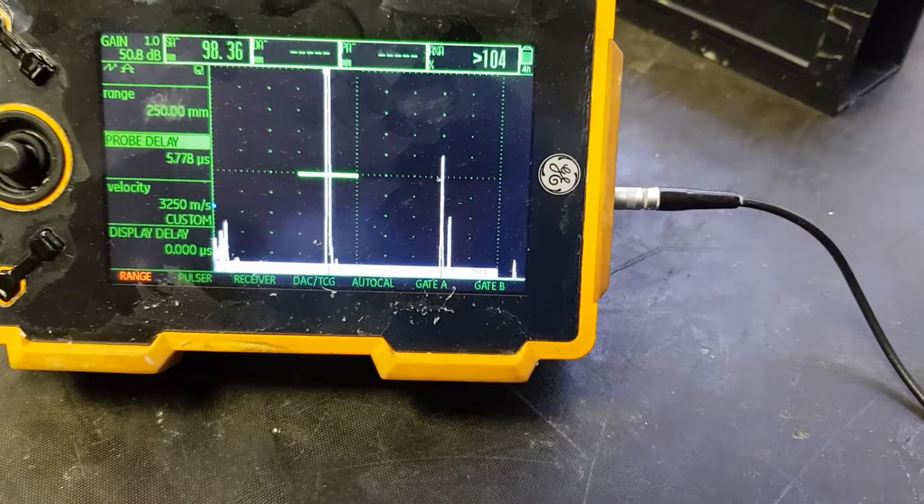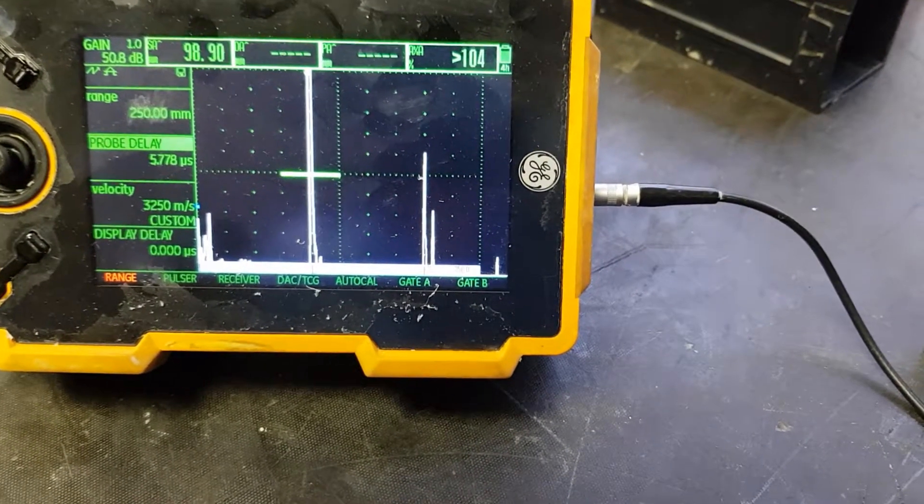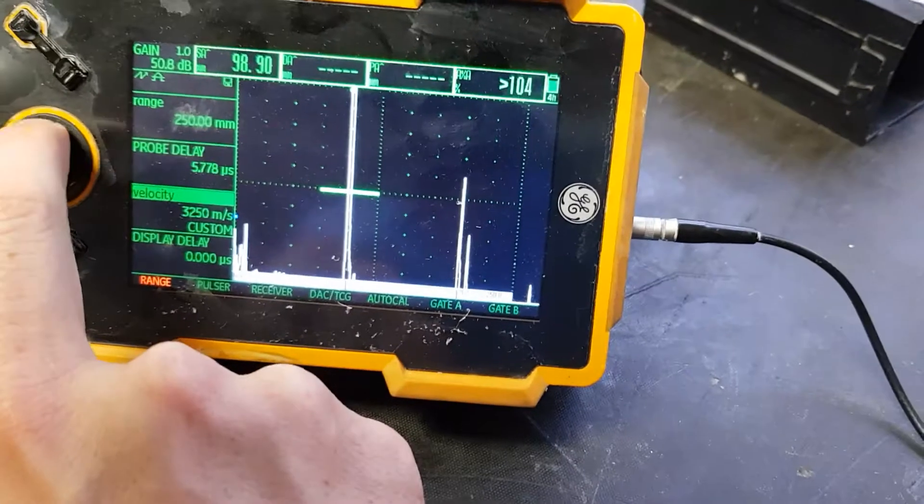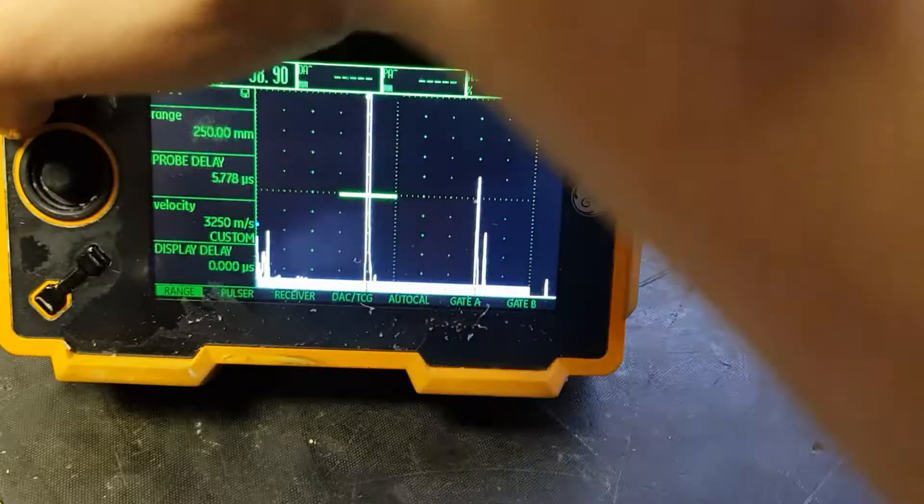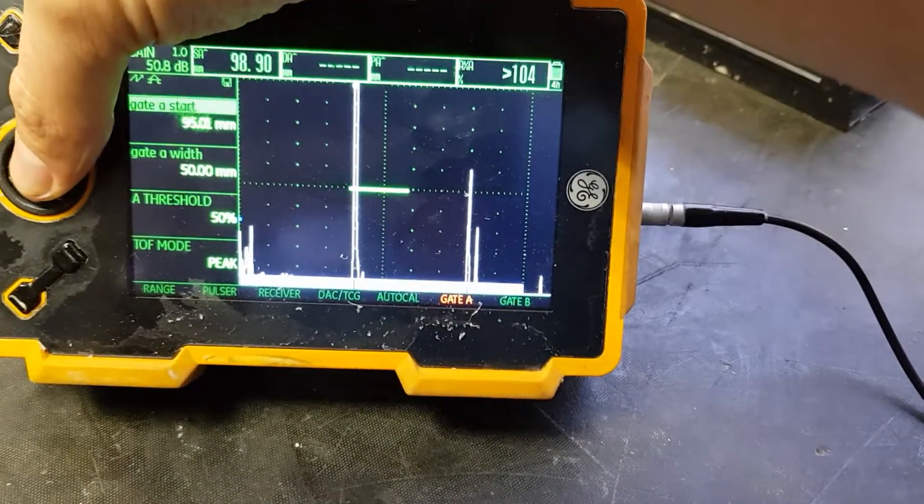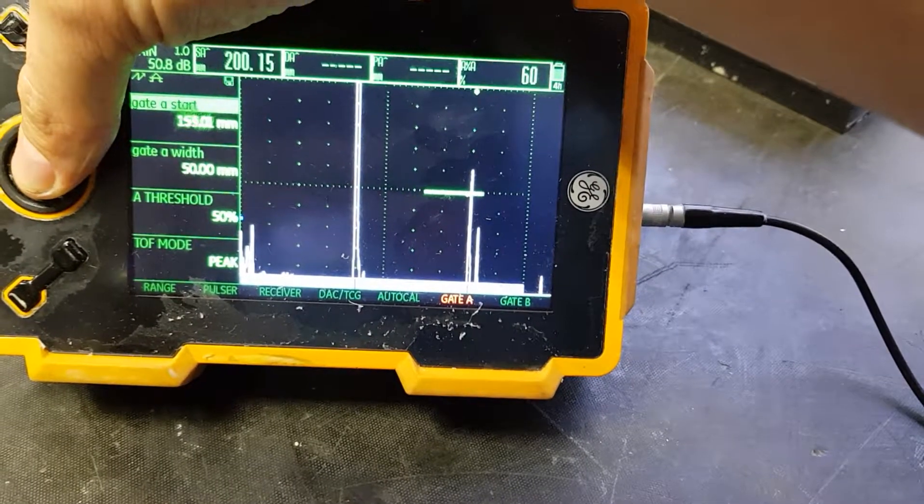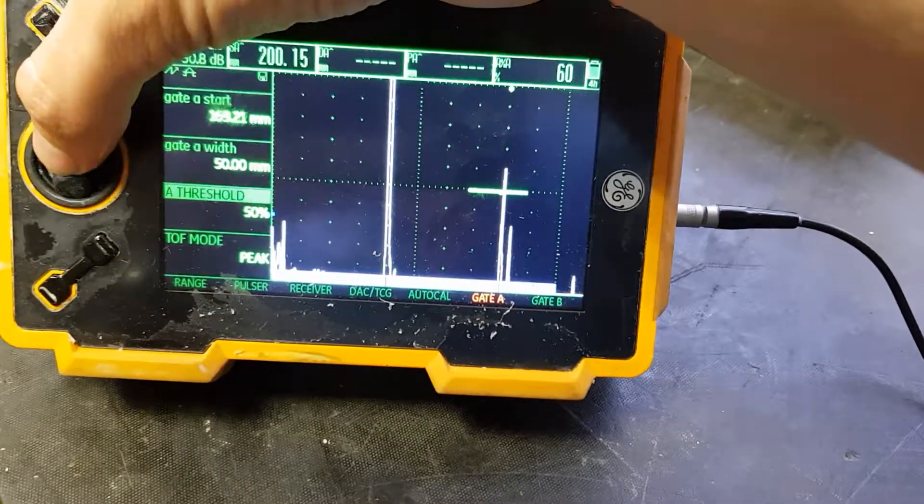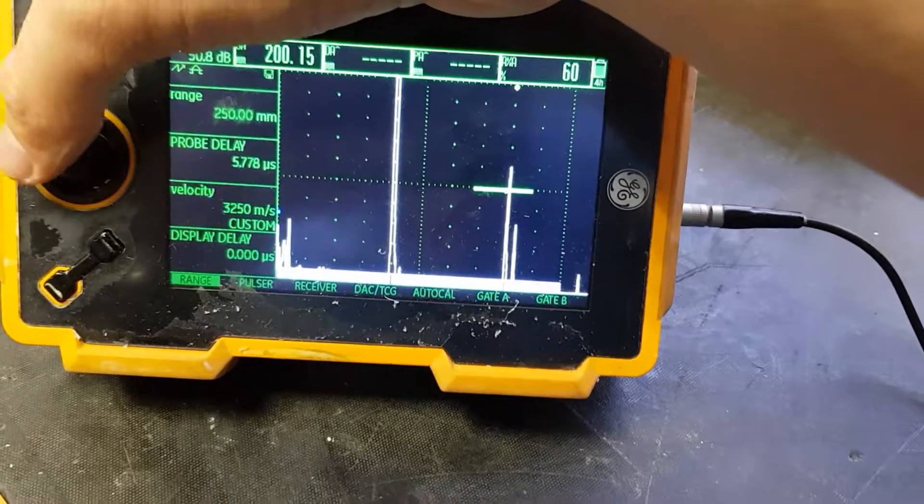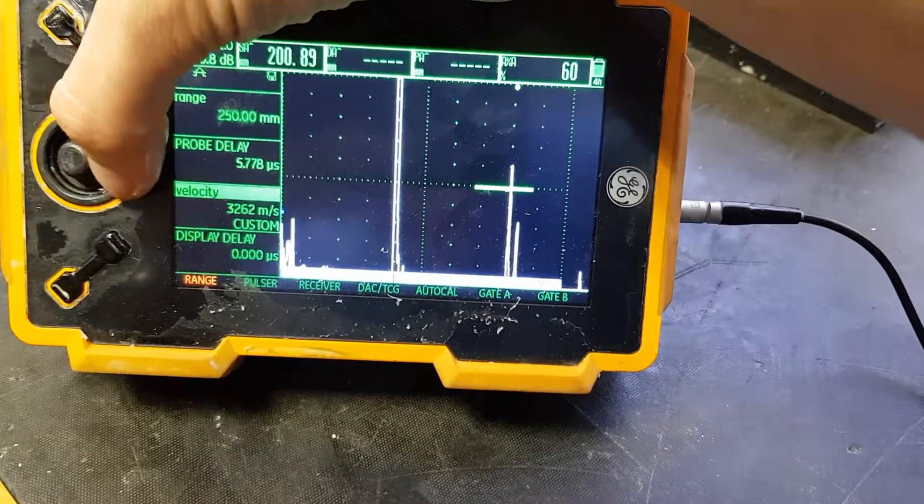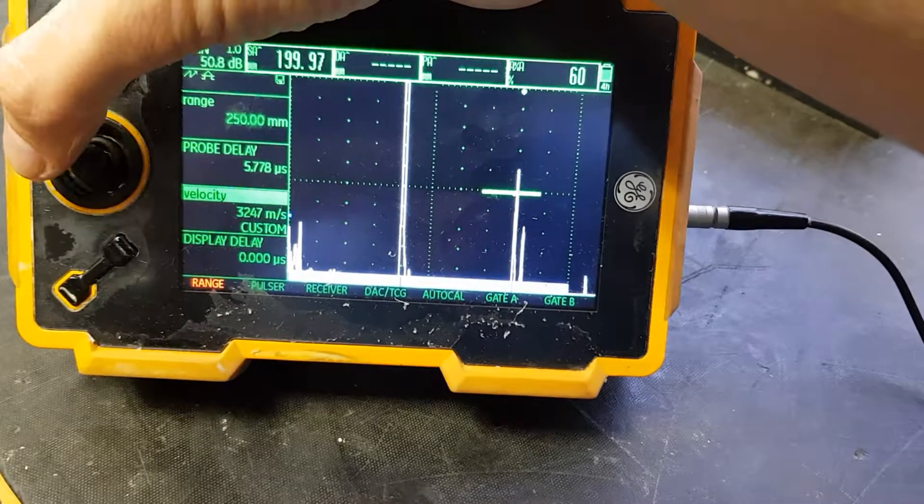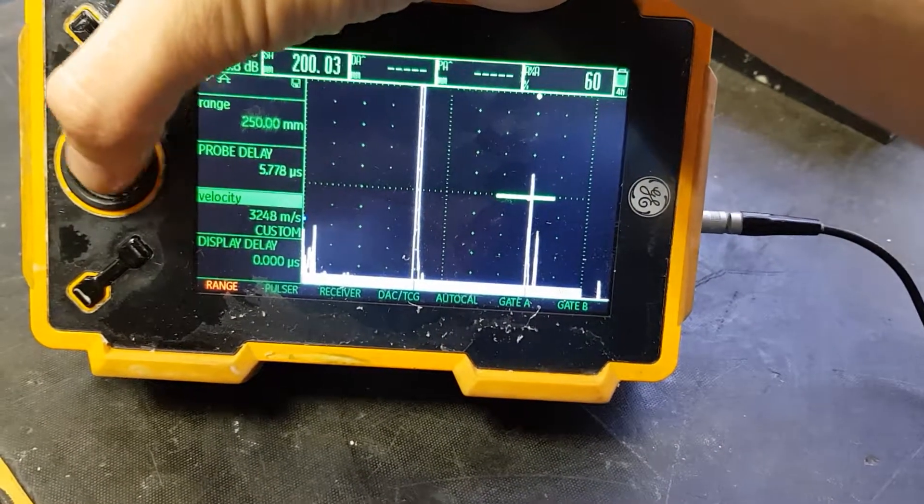We maximize the second echo as well and find its maximum. Move the gate over it to get a reading. This should be at maximum more or less 200 millimeters. We'll adjust the velocity as needed to get this to 200.